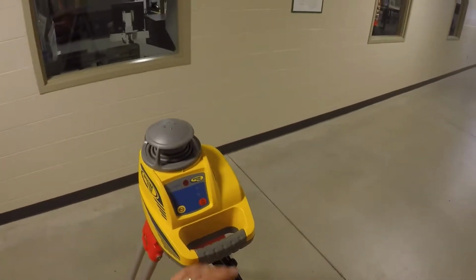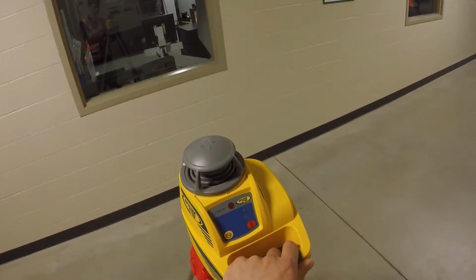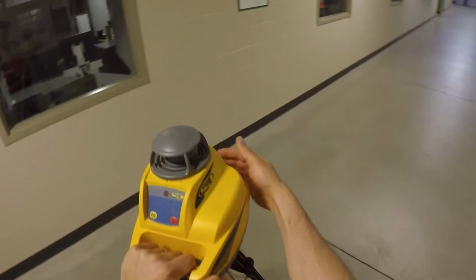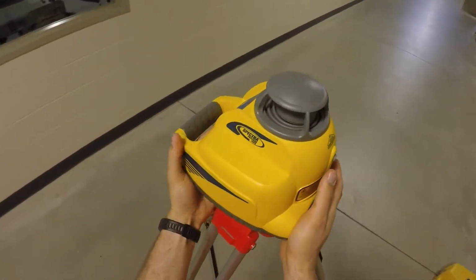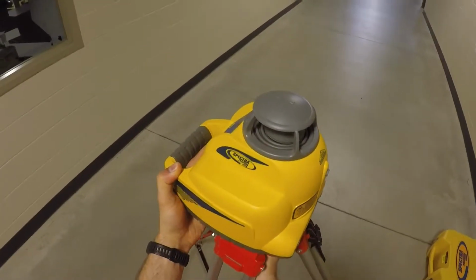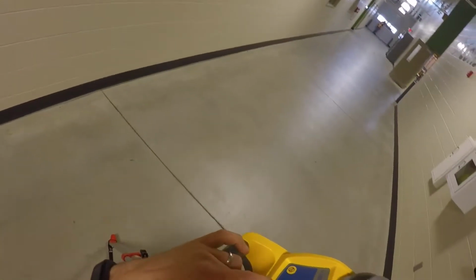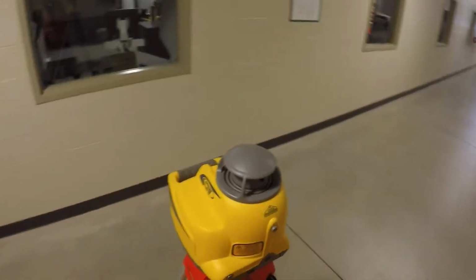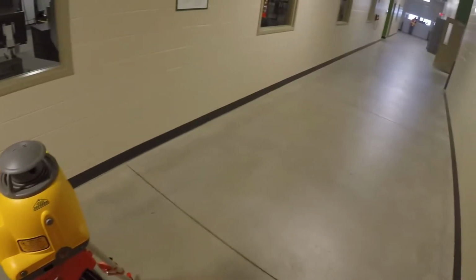Alright, so he's good, so I'm going to unclamp, rotate this instrument 180 degrees so the X is now pointing away from the wall, reclamp it, and then power up so it'll level, shoot the beam again, and if we're within calibration, it will be almost right on the same line.